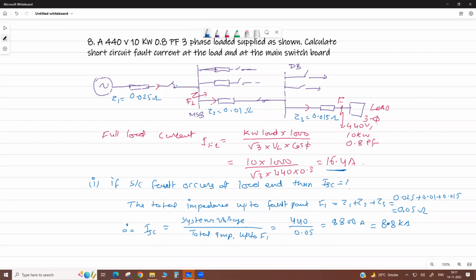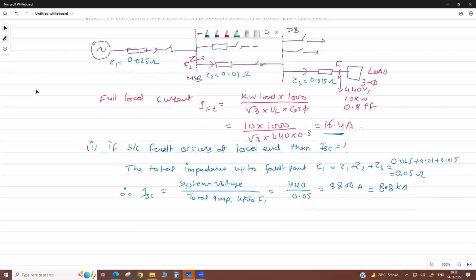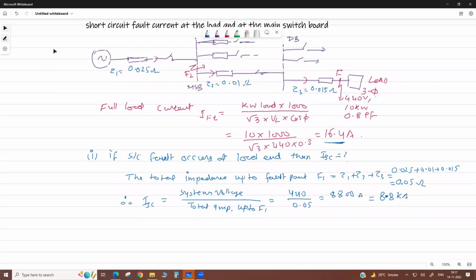Okay, that is why we do the fault calculation, for relay coordination. For relay setting, we set the breaker trip coil according to the fault calculation at different points, okay?